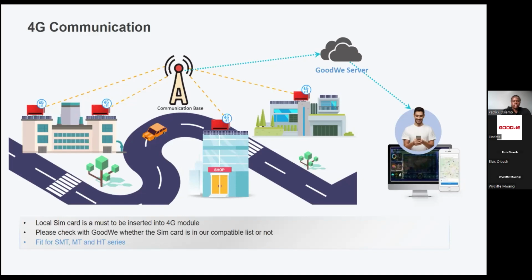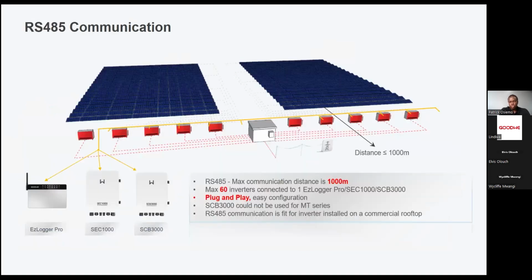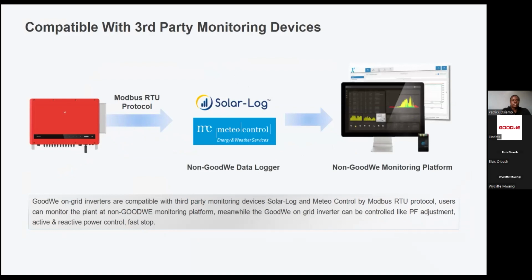That is the SMT and the HT series. And if you're doing installations which require wired connection, but the distances between the inverters are very long, then you can use the Modbus RTU protocol, which is RS-485, for distances up to 1,000 meters. And if you're using the SEC 1000, you can connect up to 60 inverters. Well, 60 inverters is quite big because we have 120 kilowatts. So if you do 60 of 120 kilowatts, do the math, that is megawatts of installations. So yes, for isolated inverters or isolated stations, you can do wireless, you can do wired. We have all those kinds of communication.